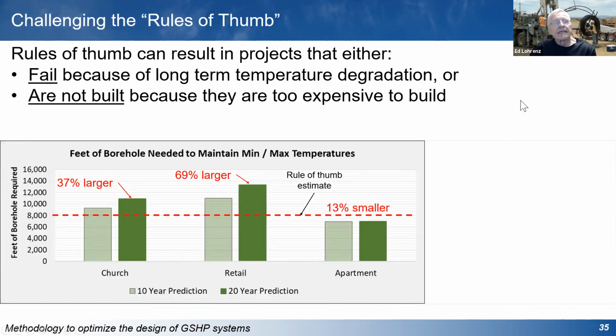So the rules of thumb, even if you build this system based on the rules of thumb, you have the danger of the ground heat exchanger for the church getting too cold, or the ground heat exchanger for the retail store getting too hot. The apartment building, because the amount of energy you're putting into the ground and pulling from the ground is going to be fairly similar over the year, you can actually reduce the size of the ground heat exchanger compared to the rules of thumb.